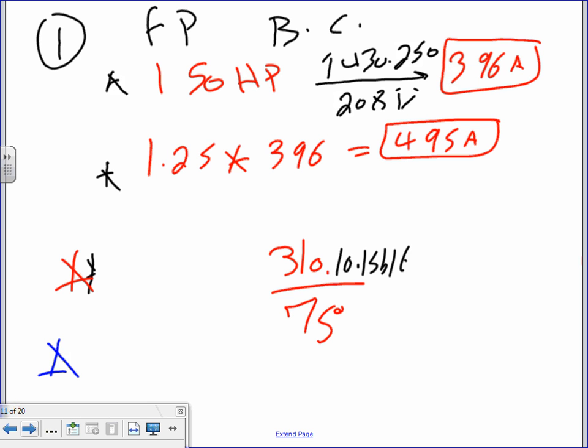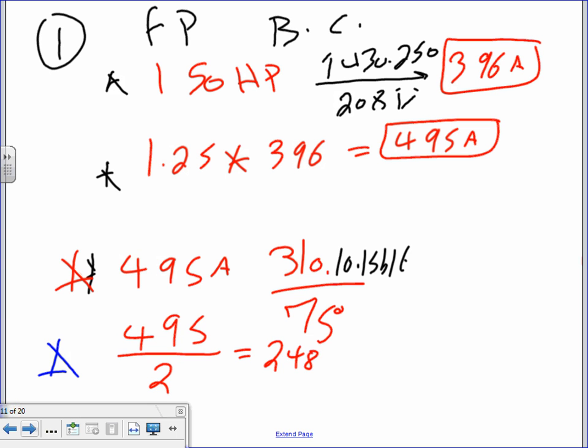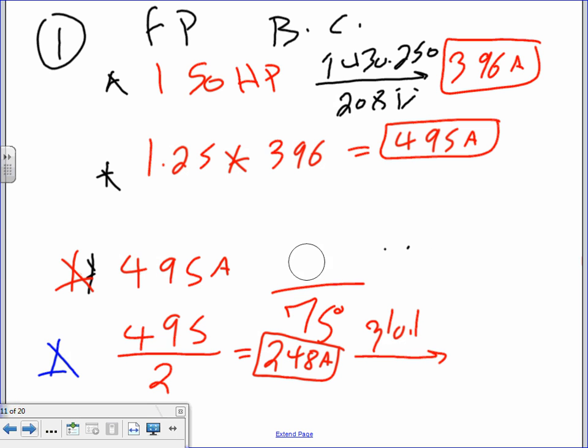We'll size the conductors. Now, Adam, you take the 495 amps, take it to 310.15(B)(16). There's one little problem. It's a lot of amps. So what do you do if it's more than 400? Derek, remind me. Thank you. We parallel. So we're going to go parallel, gentlemen. 495. How many sets? Minimum 2 in this case. So take 2 sets. That will give you 248 amps. Take this to 310.15(B)(16). We'll take it correctly.